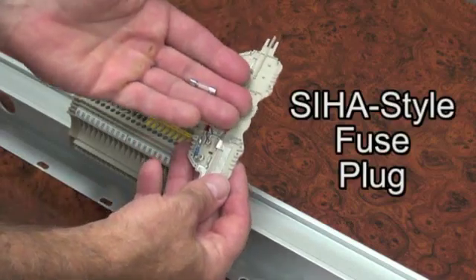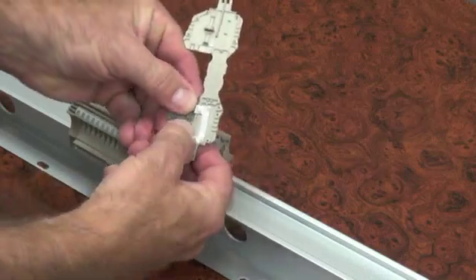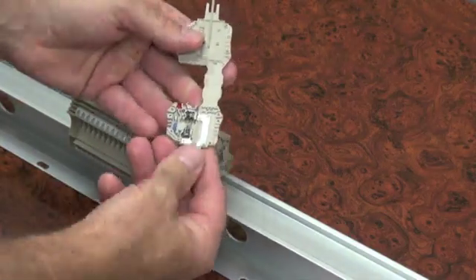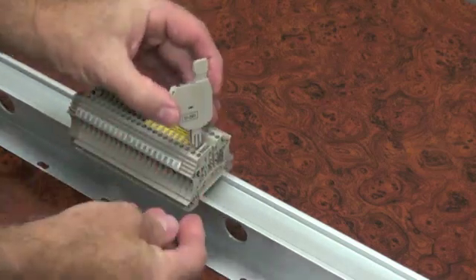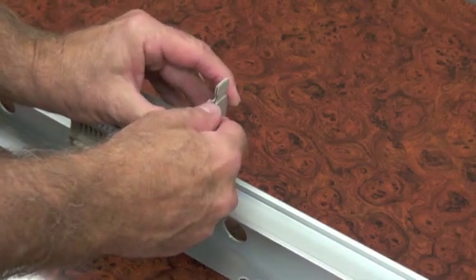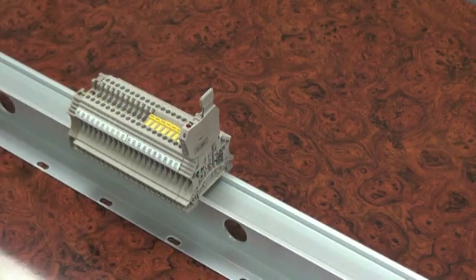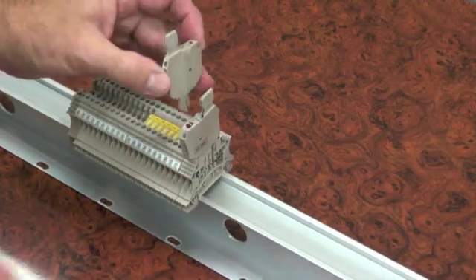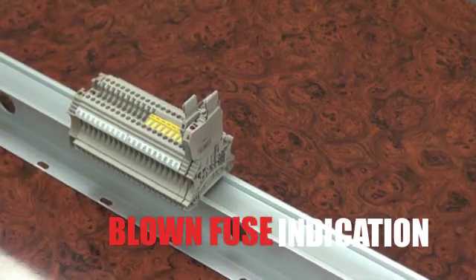This space-saving plug, with its innovative staggered design, allows the use of a 5mm fuse in only 5mm of effective rail space. The 5x20mm fuse is installed into the SIHA fuse holder, which is then fitted into the WTR 2.5 disconnect terminal block. The fuse holder in the adjacent block is inserted in the opposite direction. The SIHA fuse holder is available with or without LED blown fuse indication.